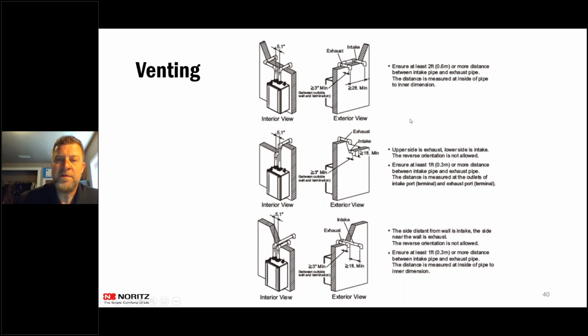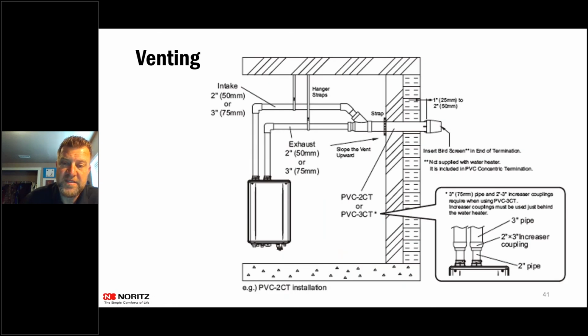What about, I've installed the vents that it blows straight out to the exhaust and then it draws the intake from behind. Are those acceptable? Yes, so next slide is the concentric venting, where you've got two pipes going into one. So this can either be installed horizontally or vertically, going out the roof or out the side.